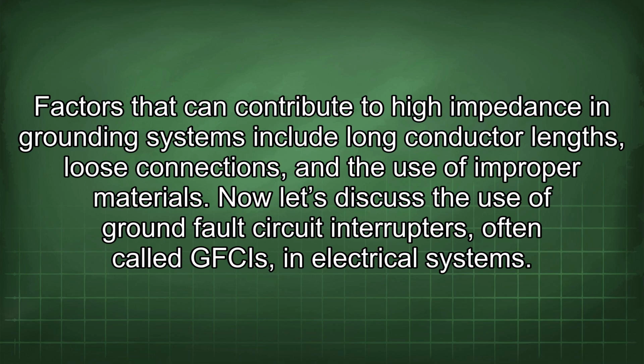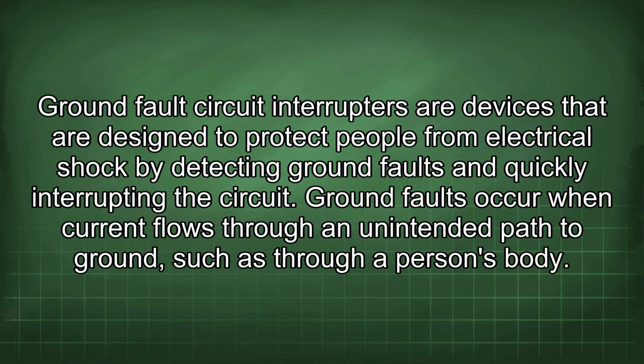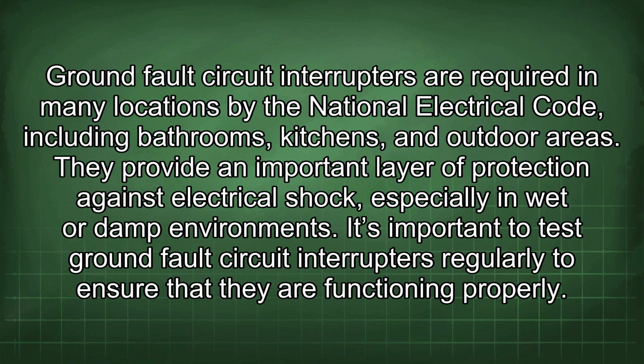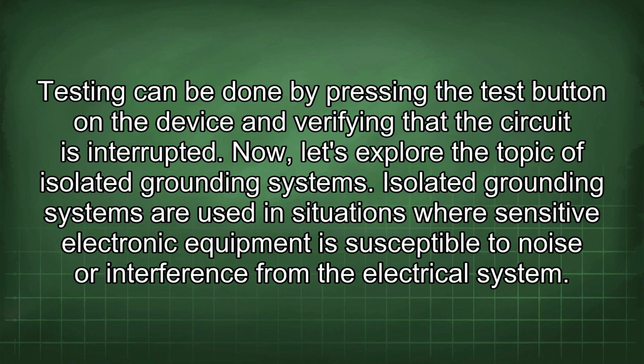Factors that can contribute to high impedance in grounding systems include long conductor lengths, loose connections, and the use of improper materials. Now let's discuss the use of ground fault circuit interrupters, often called GFCIs, in electrical systems. Ground fault circuit interrupters are devices that are designed to protect people from electrical shock by detecting ground faults and quickly interrupting the circuit. Ground faults occur when current flows through an unintended path to ground, such as through a person's body. Ground fault circuit interrupters are required in many locations by the National Electrical Code, including bathrooms, kitchens, and outdoor areas. They provide an important layer of protection against electrical shock, especially in wet or damp environments. It's important to test ground fault circuit interrupters regularly to ensure that they are functioning properly. Testing can be done by pressing the test button on the device and verifying that the circuit is interrupted.